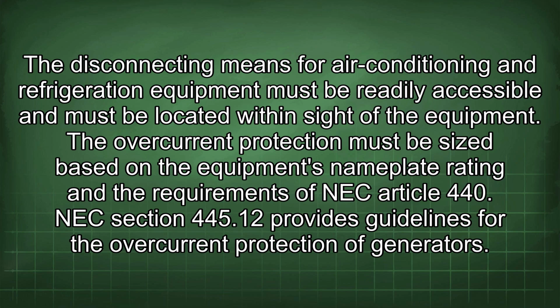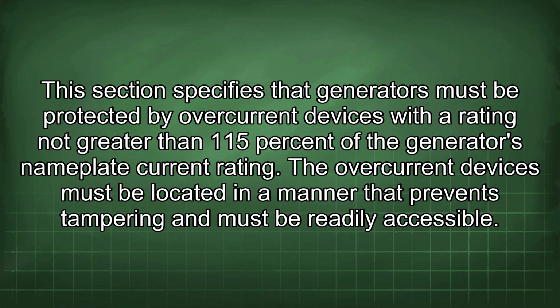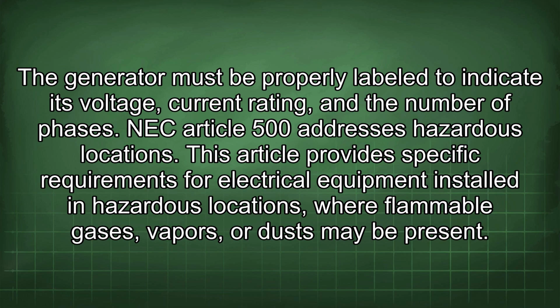NEC Section 445.12 provides guidelines for the overcurrent protection of generators. This section specifies that generators must be protected by overcurrent devices with a rating not greater than 115% of the generator's nameplate current rating. The overcurrent devices must be located in a manner that prevents tampering and must be readily accessible. The generator must be properly labeled to indicate its voltage, current rating, and the number of phases.